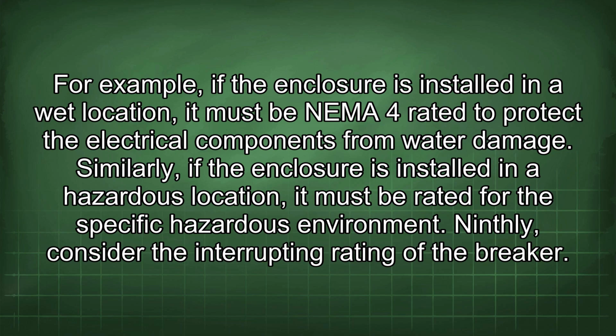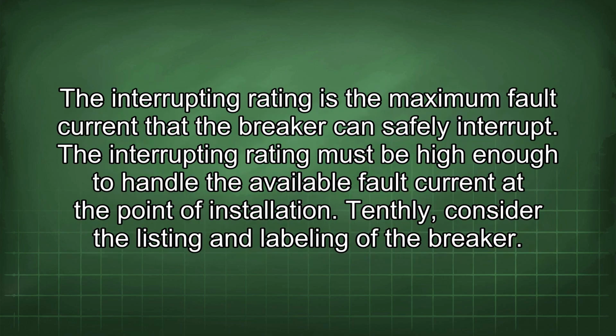Ninthly, consider the interrupting rating of the breaker. The interrupting rating is the maximum fault current that the breaker can safely interrupt. The interrupting rating must be high enough to handle the available fault current at the point of installation.